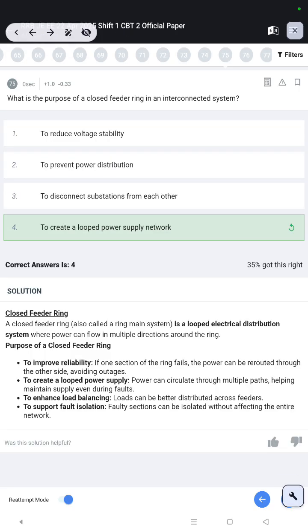Closed feeder ring. A closed feeder ring, also called a ring main system, is a looped electrical distribution system where power can flow in multiple directions around the ring. Purpose of a closed feeder ring: to improve reliability, to create a looped power supply, to enhance load balancing, to support fault isolation.